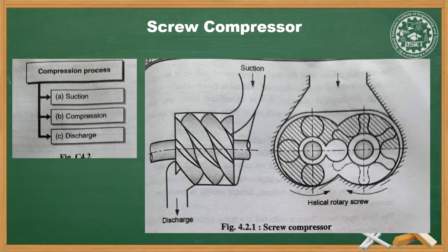This type of compressor gives smooth and continuous flow of air due to intake and discharge cycle overlap. It has low maintenance due to fewer moving parts, is smaller in size, lighter in weight, and has stepless capacity control, less starting torque, no need of balancing, less wear and tear, as well as less vibration.